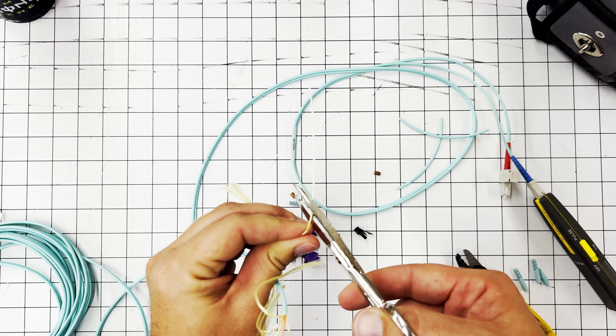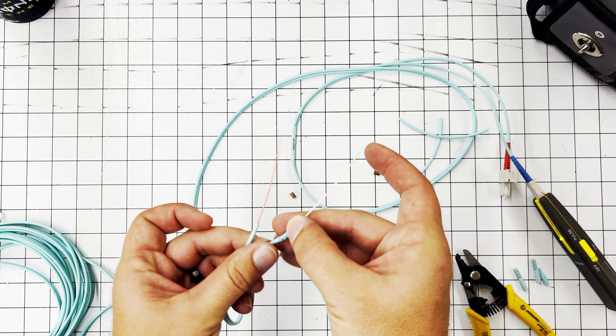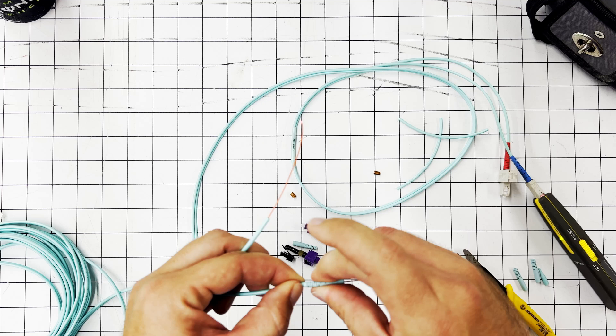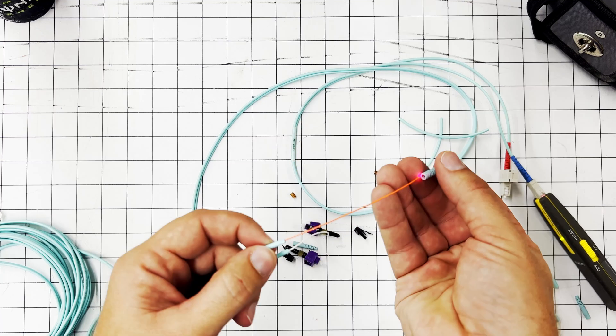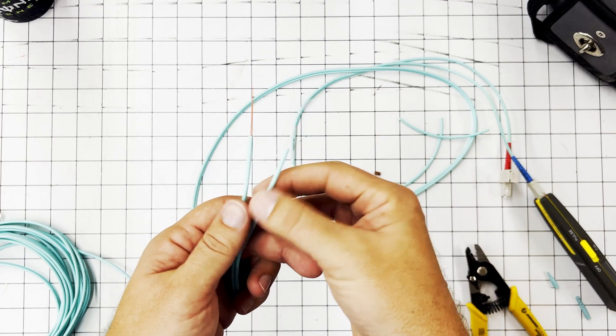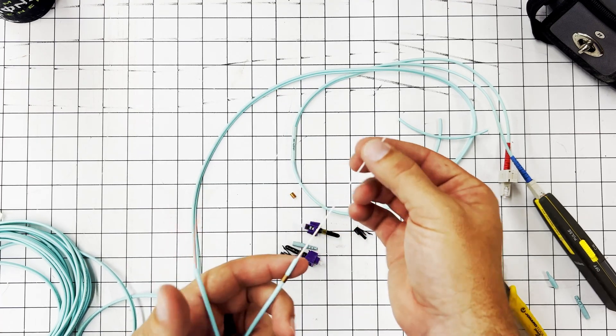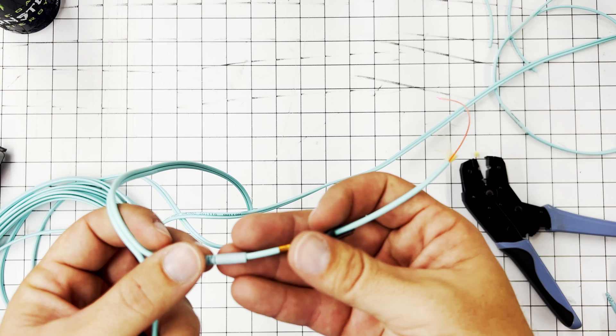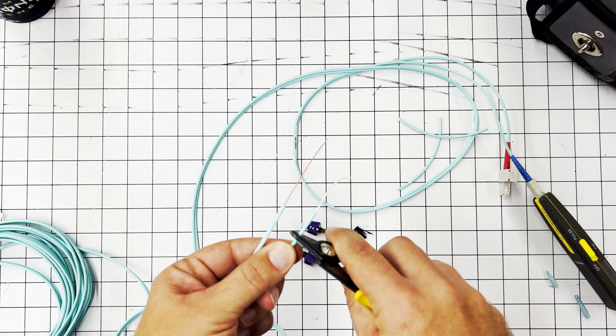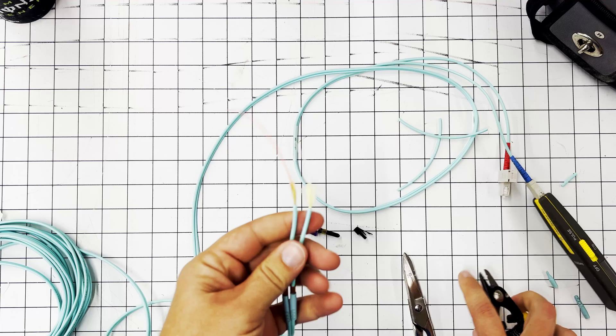We cut the yarn off. That way we can get a good measurement. We're going to try the medium. And it looks like it's going to go. But just not quite. It is just a hair too tight. I might be able to get it on there after a while working it. But it is just too tight. So we're going to use the larger one. And we're going to run it all the way up. And then this one as well. Get yourself a little bit of slack too. And now we're going to put the copper collars on. Alright so you got the boot. The collar. And the snag resistant claw here. And now we're going to strip this out and terminate it. So now we're going to get a little bit more yarn. And we're just going to cut about an inch. Maybe three quarters of an inch. Make sure they line up about the same. That's pretty good.